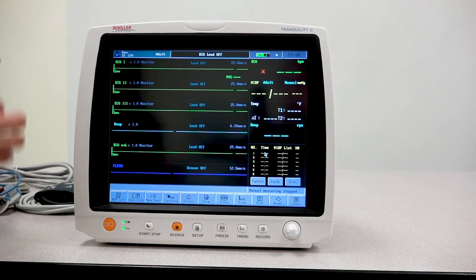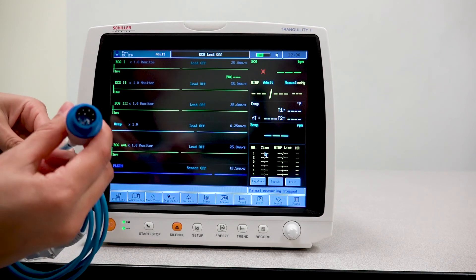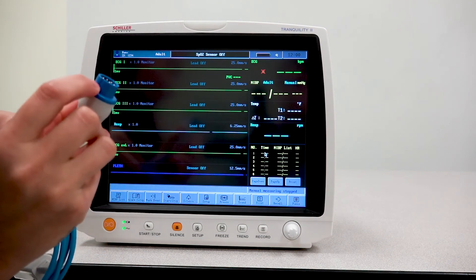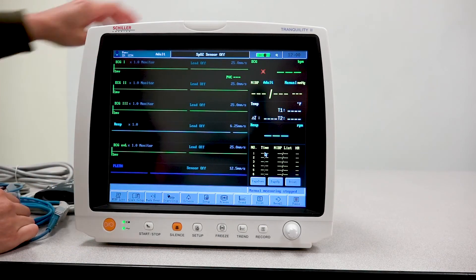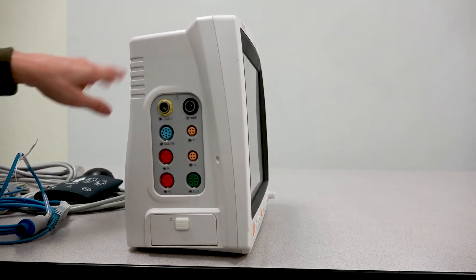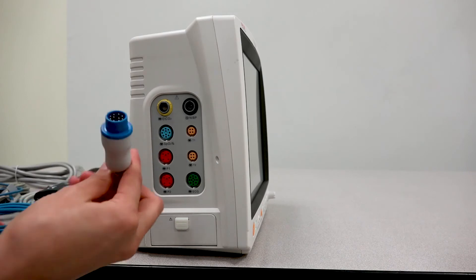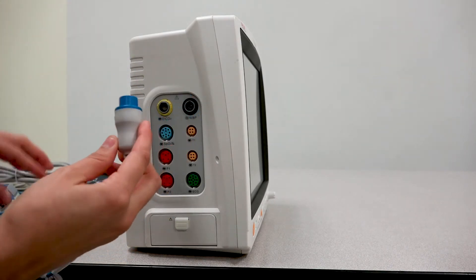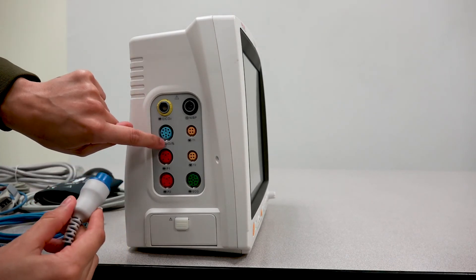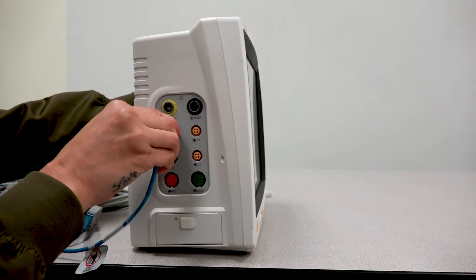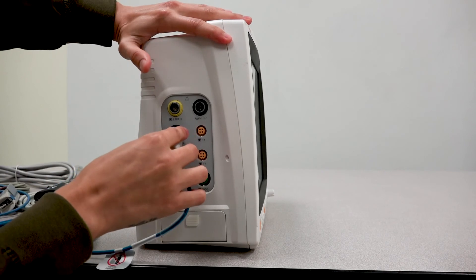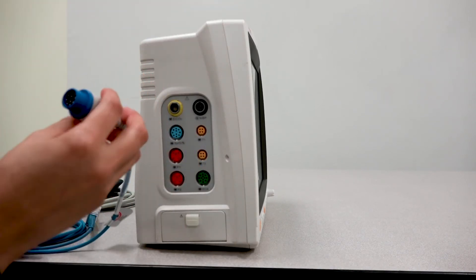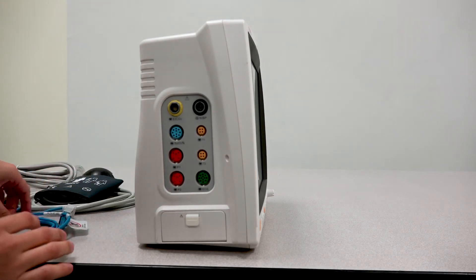On the other end that attaches to the monitor, I wanted to point out the grooves here. You have to be mindful of the grooves on these connectors because if you notice on the side where the parameters are, each connector has a groove as well that must align with the groove of the connector on the actual accessory. For example, the groove is down here, so is the one on the connector toward the bottom. Just make sure they align. If you feel any type of resistance, please stop because you might be inserting it incorrectly and you can definitely damage the pins or connectors.